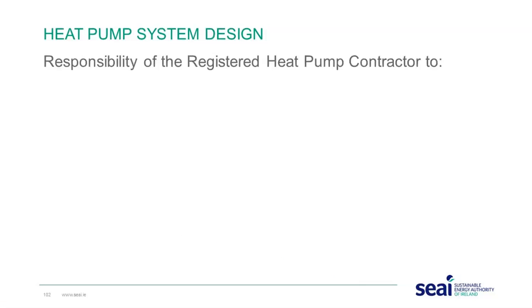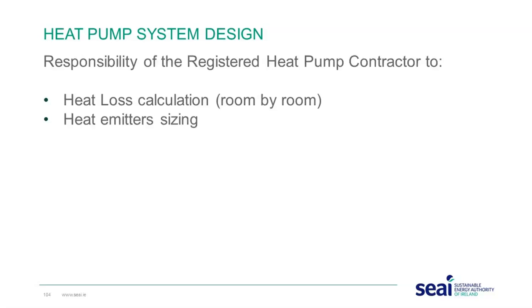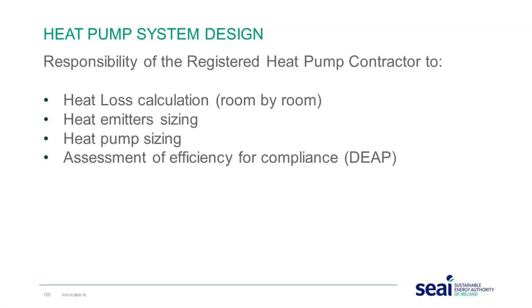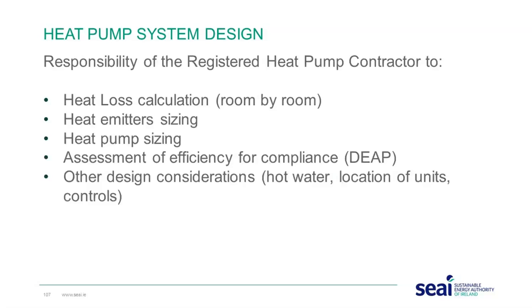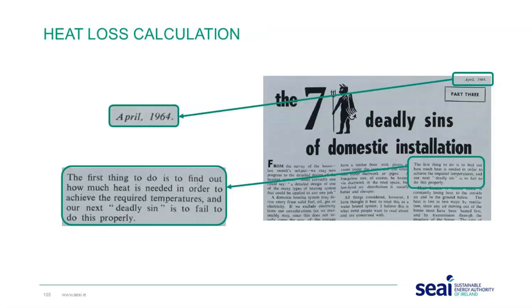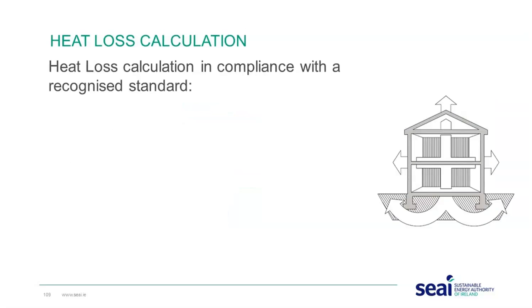So if we look at the heat pump system design, it's the responsibility of the registered heat pump contractor to do the following: to do the heat loss calculation on a room by room basis, to size the heat emitters, to size the heat pump, to assess the efficiency of the heat pump for compliance, that's done through DEAP, and other design considerations such as the hot water, the location of the units, and the controls of the system. So just to give you a bit of background, when we talk about heat loss calculations, this is taken from an engineering journal that was written in 1964, so it's over 50 years ago. And the same things have been spoken about that we speak about today. It's how design is essential when we're looking at heating systems, and even more so now we're talking about heat pumps. So how do we go about our heat loss calculations?